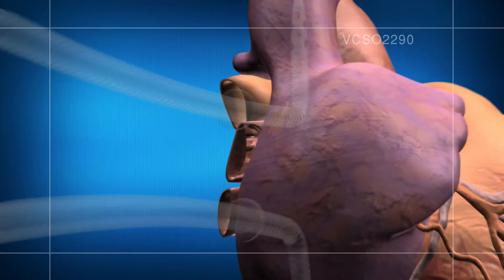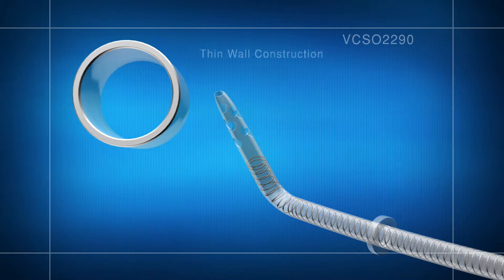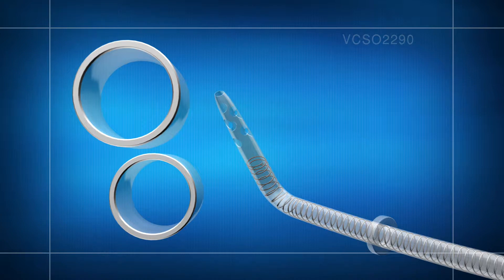The AVID single-stage venous return cannula was designed specifically for assisted venous drainage. This design includes a unique tip hole design providing optimal flow rates and proprietary thin wall construction. The 22 French diameter maximizes surgical space in the surgical field.